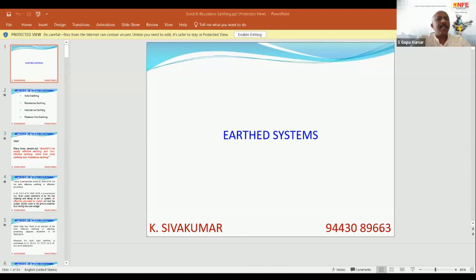Yeah. Sir, then there is a question: how can we test the effectiveness of a solidly earthed system? Okay, solidly earthed system. Earth resistance only; you measure the neutral to earth resistance. In a resistance earthed system, it will be very high. In an effectively earthed system, the resistance value should be as low as possible. That's all. How else will you? Yeah, resistance only. Effectively, we call it resistance. The resistance should be as low as possible. That is the definition given in IS 3043. You measure the resistance, the neutral ground resistance.